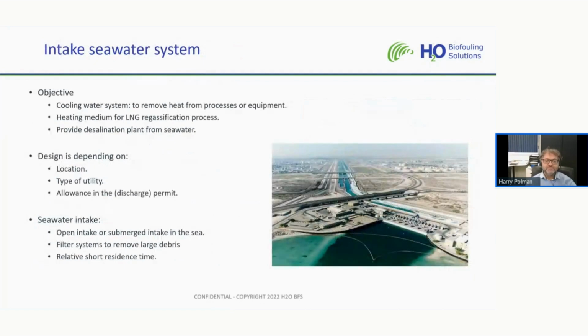Seawater intake systems have the objective, as mentioned, to cool systems, remove heat from the processes or equipment, provide heating medium for LNG regasification plants, or provide a source for desalination plants to produce potable water. The design of an intake depends very much on the location, the type of utility, and also the allowance in the discharge permit. Intakes often are open intakes, as you can see on the picture on the right. This is one of the biggest cooling water systems in the world. It's in Jubail, Saudi Arabia.